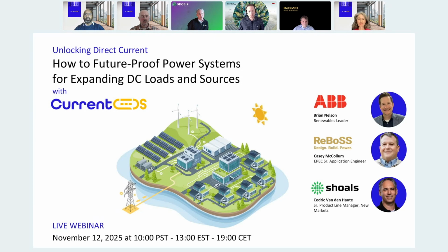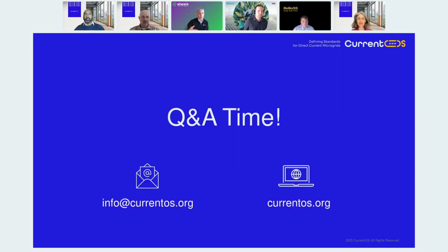You have fewer conversion units inside the racks, and that's more space for your equipment. So on one hand, you have systems that are becoming extremely crowded, but DC has the potential to simplify, use less material, and be more sustainable. It's about all the problems that it solves at once. It's not using DC for the sake of using DC, but everything that it allows you to do in the space.